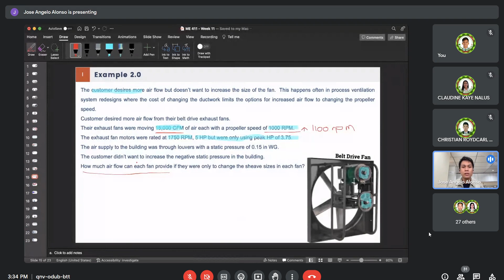Okay? So we did not reduce the pressure, class; rather, our pressure even increased, since the customer didn't want to increase the negative static pressure in the building. Unfortunately, we increased the pressure here. Okay? But what the problem really asks for is to determine the new flow rate, meaning what we got, class, is 11,000 cubic feet per minute, or the 10% increase.